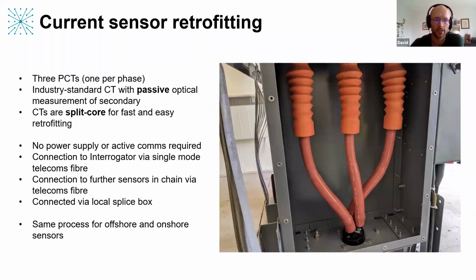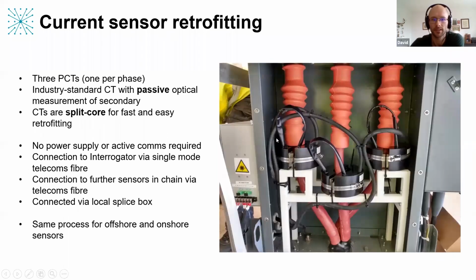The current sensors have been retrofitted, as I said, in the substation, onshore, and in the turbine itself. 3 sensors, one per phase, have been installed. These are industry standard CTs connected to our unique passive optical measurement devices, which connect to the secondary of these CTs. The CTs installed here were split core, which enabled a really fast installation and easy retrofitting. At this point here, we don't require any power supply or active communication systems because these sensors are inherently passive.